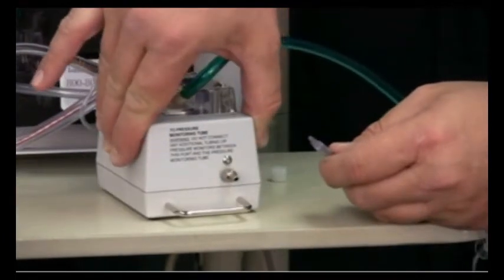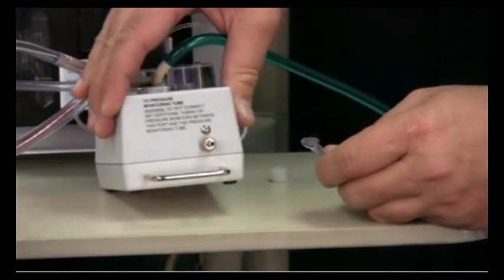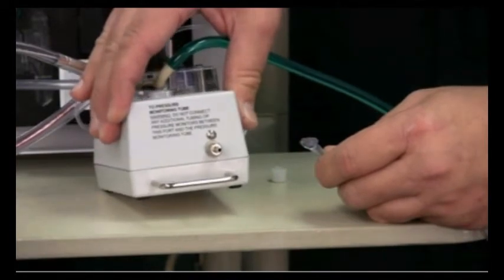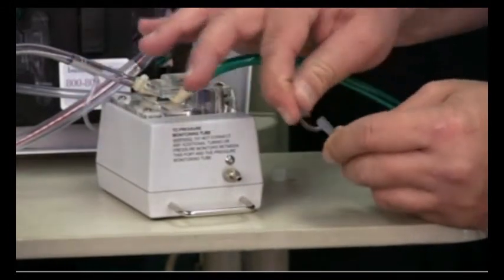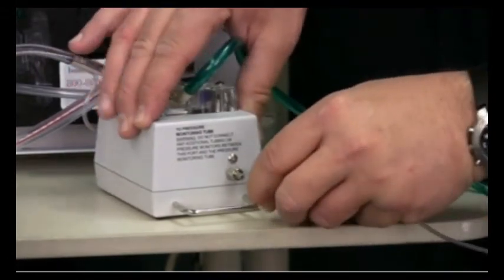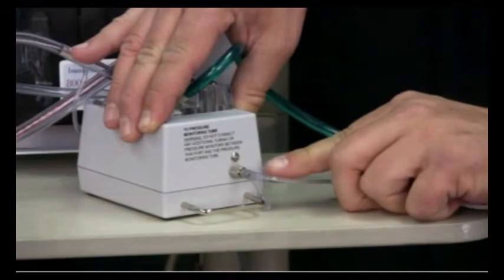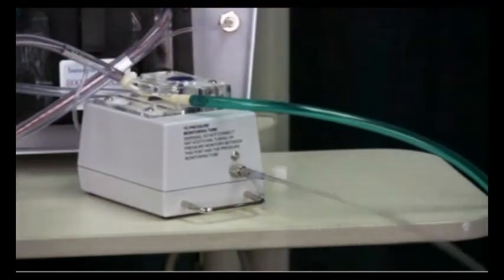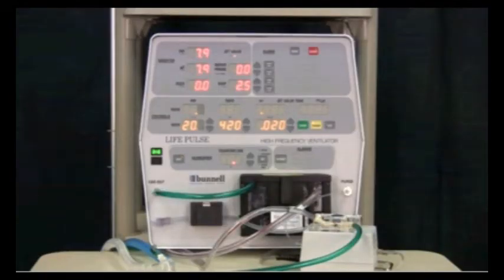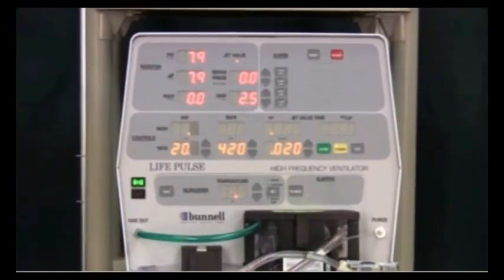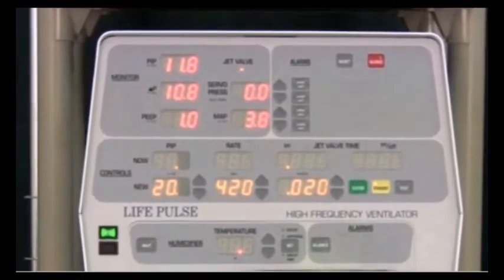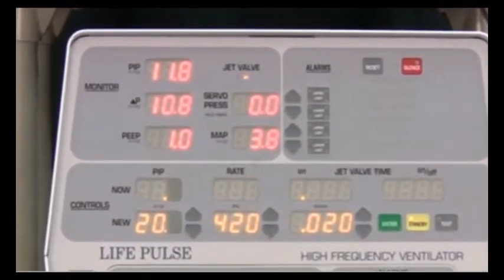Connect the pressure monitoring tube of the LifePort adapter to the patient box and connect the LifePulse circuit to the jet port on the side of the LifePort adapter. Once the pressure monitoring tube of the LifePort adapter has been connected to the patient box, the LifePulse, in its standby mode, will begin to monitor the pressures being delivered by the conventional ventilator or other high-frequency ventilator, and it will update them in the monitor section every 10 seconds.